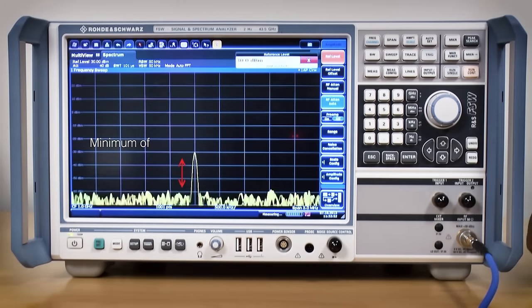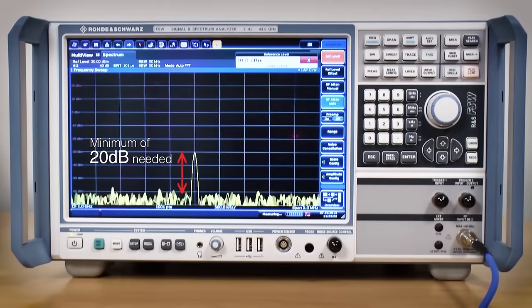Typically, a minimum figure of 20 dB between the signal and noise is required for good measurements. Much closer to the noise, and the signal level will be seen to vary, because the noise level is sufficient to add to the signal and affect the overall result.